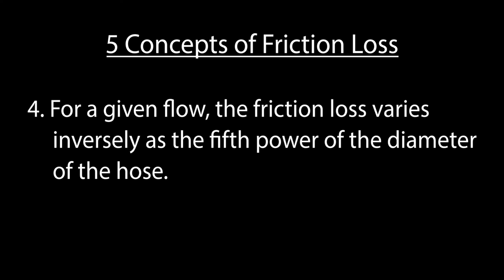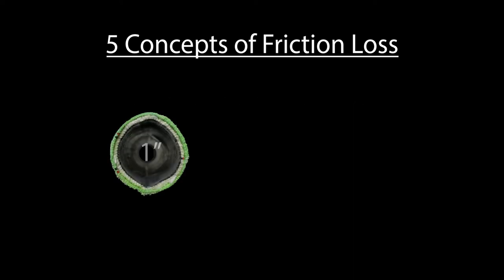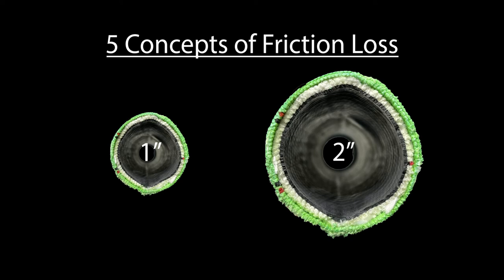The fourth concept states that for a given flow, the friction loss varies inversely as the fifth power of the diameter of the hose. Simply put, if the flow is kept constant, if the hose size is doubled, the friction loss is only 1/32nd of the smaller hose.